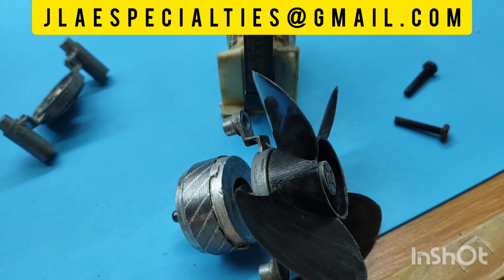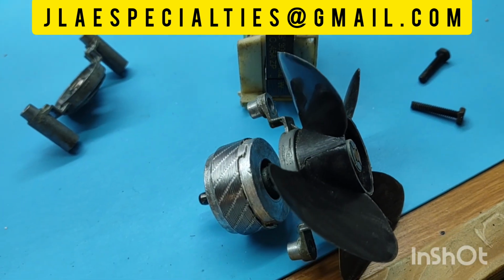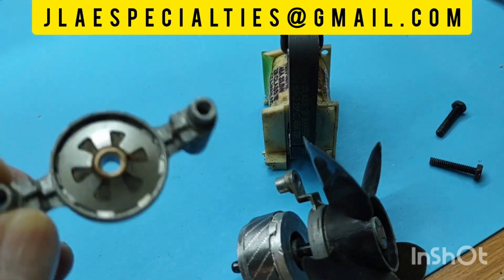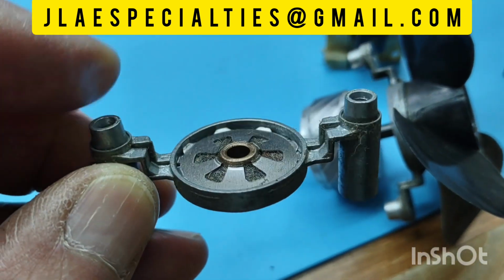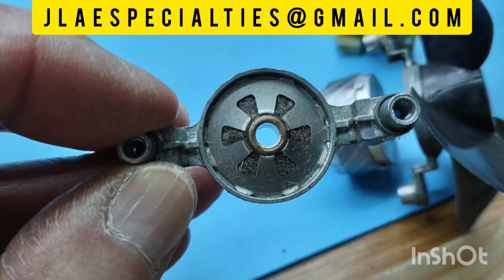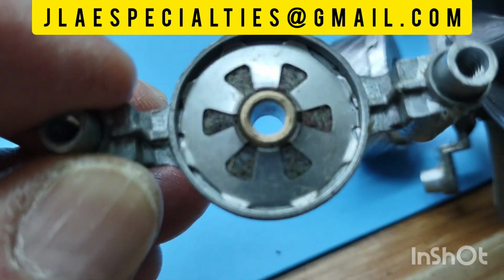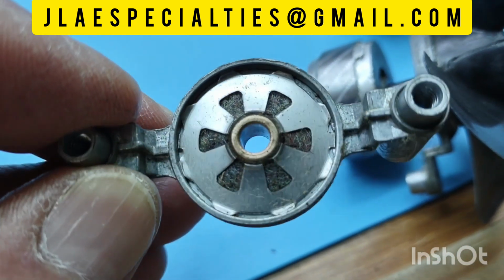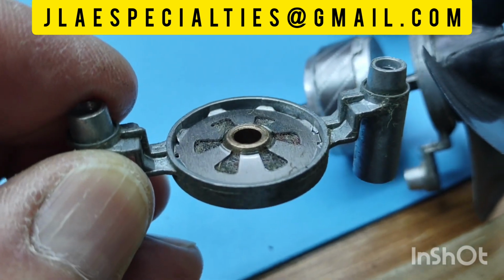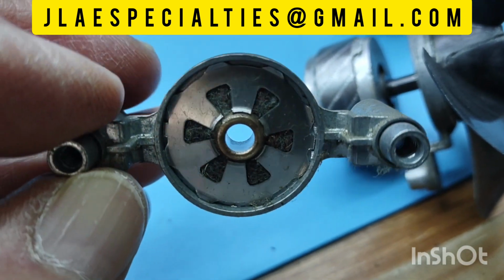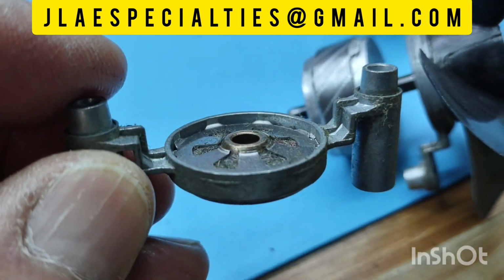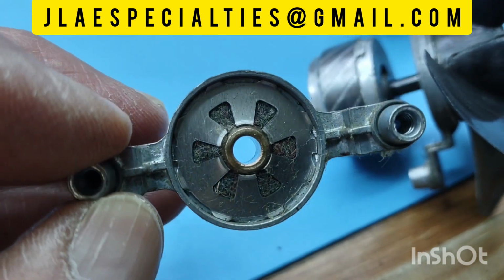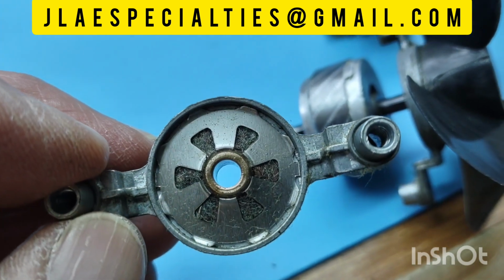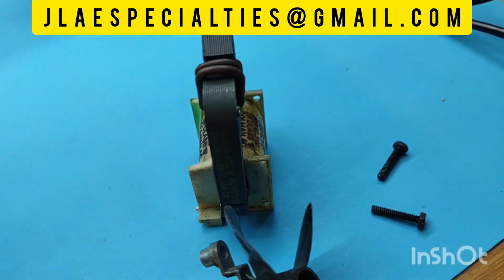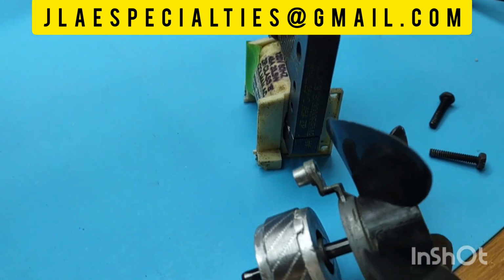At the same time, I've got the fan out. It's actually working, but when you spin it, it's kind of binding. In each end where the bushing is for the shaft, there's felt down inside, and that dries out. This provides lubricant for the bushing. So we're going to add some lubricant into that felt, clean everything up, which I've already done, and this motor will be good as new.